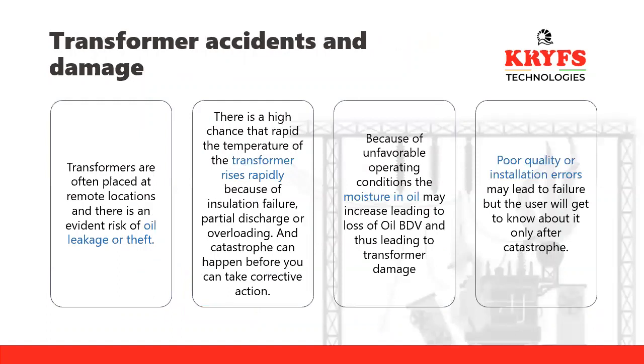Talking about transformer accidents and damage, transformers are often placed at remote locations, and there is a risk of oil leakage and theft. This is one of the major problems for major utilities in India, Africa, etc. There is a high chance that rapid temperature rise of the transformer can cause insulation failure, partial discharge, or overloading. And catastrophe can happen before you can take corrective action. Because of unfavorable operating conditions, moisture in oil may increase, leading to loss of oil BDV and thus transformer damage. Poor quality of installation or installation errors may lead to failure, but the user will get to know only after the transformer has already been damaged. This was about the accidents.